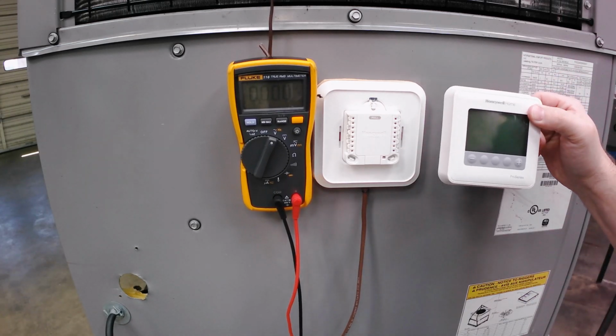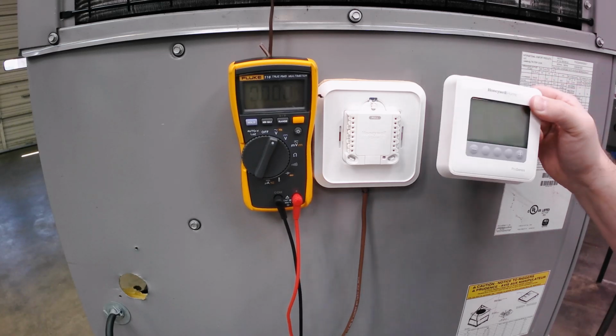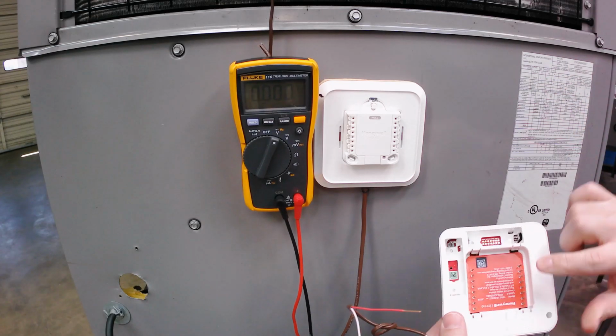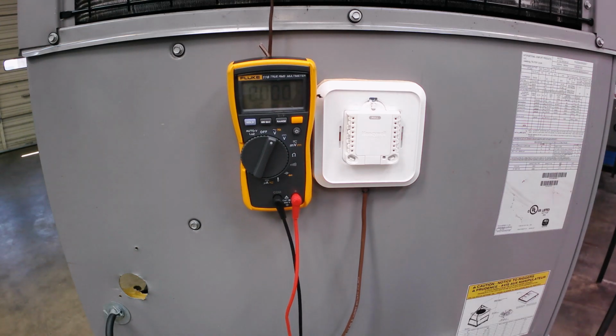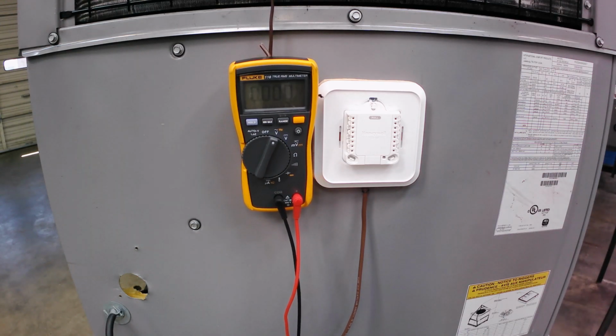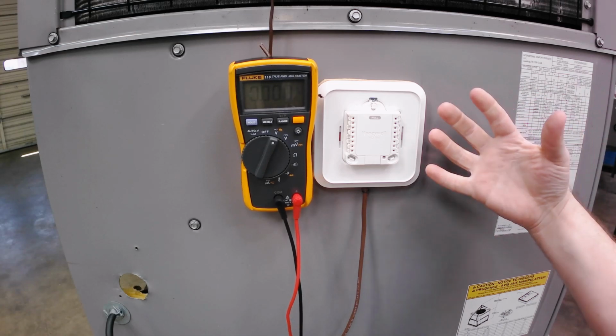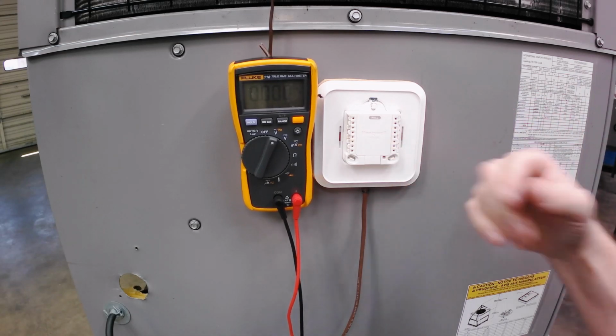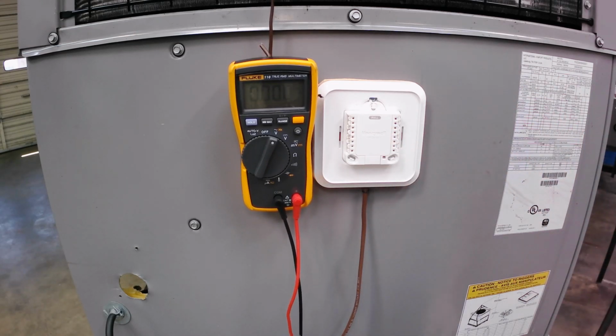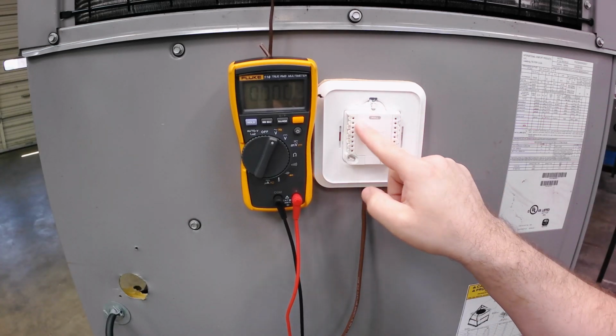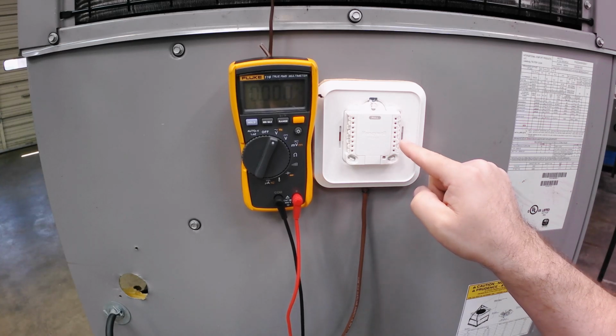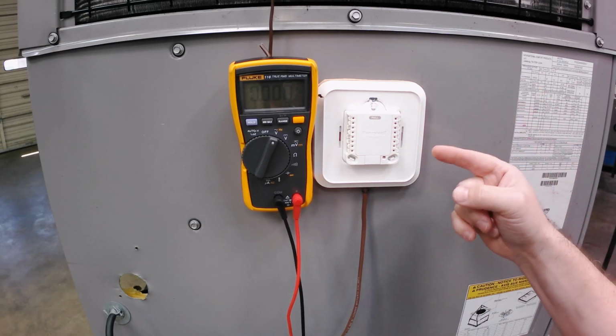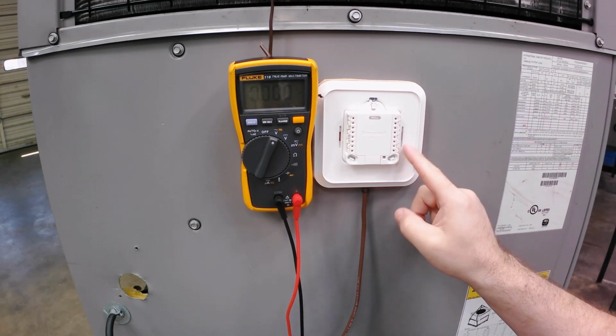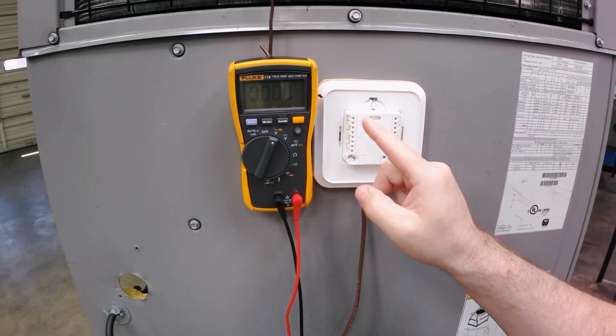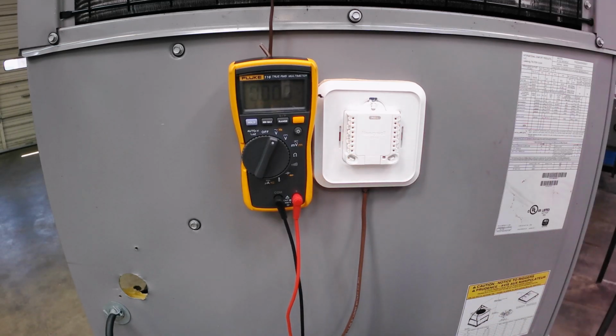When you remove the faceplate off of a thermostat, you pull all the switches. That circuit board in here, if it's old school with mechanical switches or something, you are removing that from in between the wire. You are removing it from the circuit, and you're going to get 24 volts on everything, but all you really have is power on R. So don't look at it as R is passing power to G, or R is passing power to Y or W, because it's not.